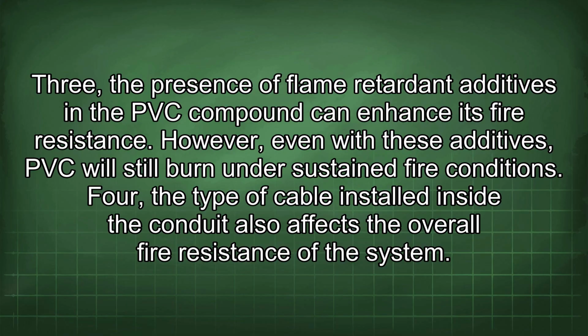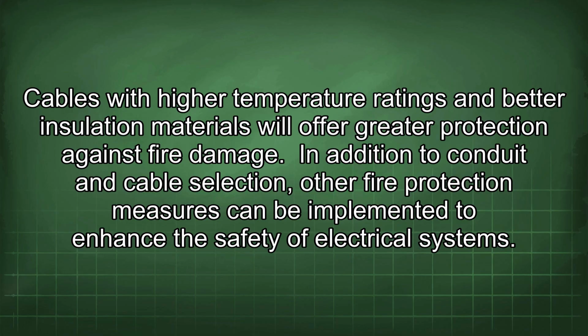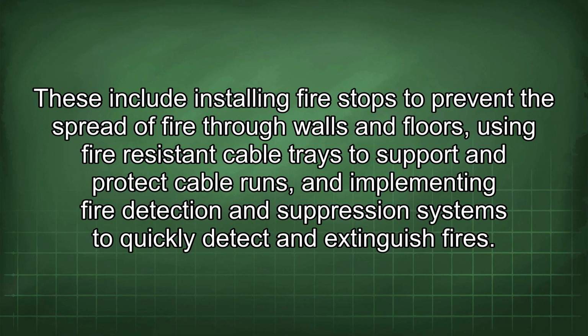4. The type of cable installed inside the conduit also affects the overall fire resistance of the system. Cables with high temperature ratings and better insulation materials will offer greater protection against fire damage. In addition to conduit and cable selection, other fire protection measures can be implemented to enhance the safety of electrical systems. These include installing fire stops to prevent the spread of fire through walls and floors, using fire-resistant cable trays to support and protect cable runs, and implementing fire detection and suppression systems to quickly detect and extinguish fires.